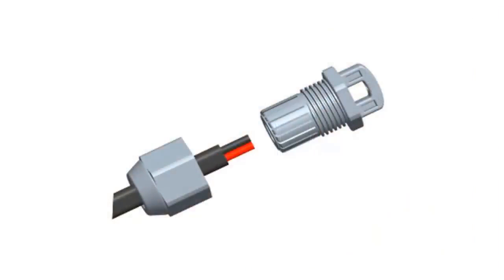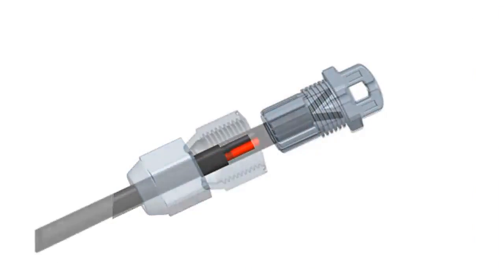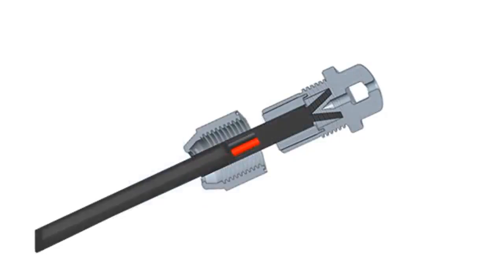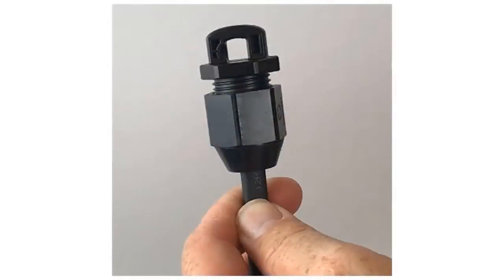Insert the cable into the terminator body so that each of the 2 wires land on opposite sides of the internal separator. The grommet inside the terminator body should remain in place. Verify that the opening of the grommet is aligned with the flat of the cable, so that when inserting the wires, they are split by the internal separator. Make sure that the hex nut is fully tightened.